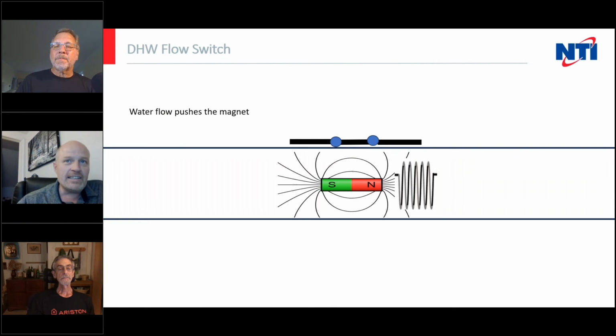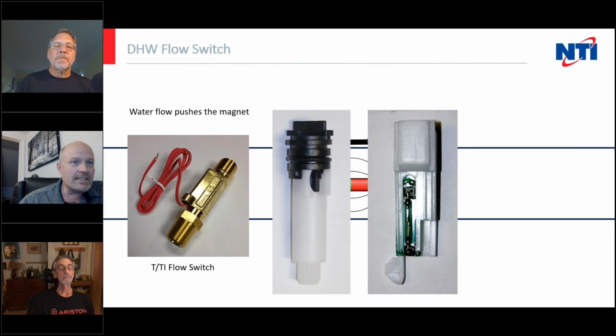And it literally is, if you were to put a magnifying glass on there, the reed switch doesn't look all too different to what I show here. It's just two pieces of iron wire. One sits on top of the other. There's a slight bend in one of them so that they don't touch, and then when you stick the magnet under, they do touch. So the flow switch is very basic. This is an old TI series flow switch. In this, where the two red wires go epoxied in there is a reed switch.